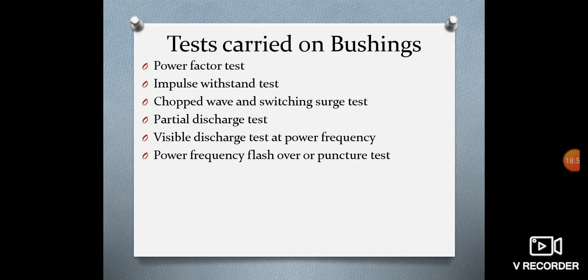Okay, and we have the visible discharge test at power frequency. The test is carried out to ascertain whether the given bushing will give rise to radio interference or not during operation. The test is carried out in a dark room. The voltage as specified is applied to the bushing as per IS 2099. No discharge other than that from the grading rings or arcing horns should be visible.